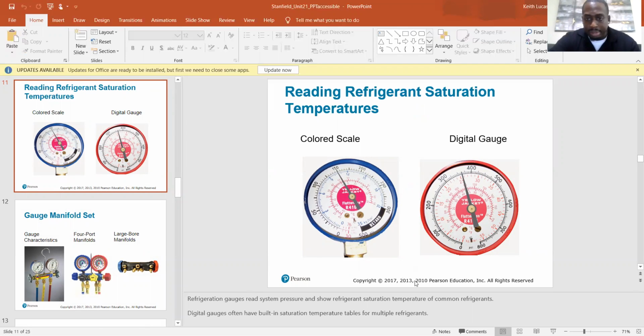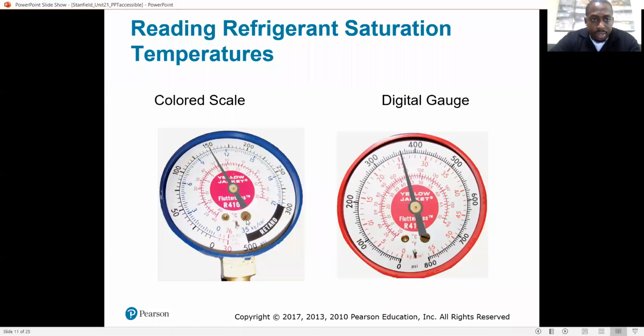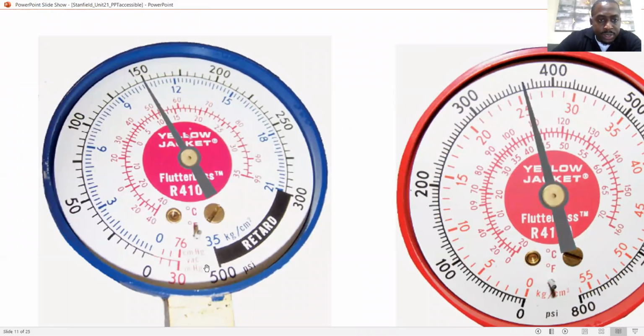Meaning, let's see if I can make this a little bigger. Okay, so let's take 410A, for example. 410A at 150 PSI gives us a saturation temperature of a little over 50 degrees. So if that's 60, then I'm going to say this is 52. 410A refrigerant at 150 PSI gives us a saturation temperature of 52 degrees. That same refrigerant, if it were at 100 PSI, would give us 30 degrees of saturation temperature. So that's what the gauges are showing you.